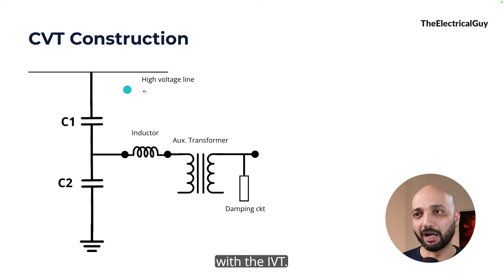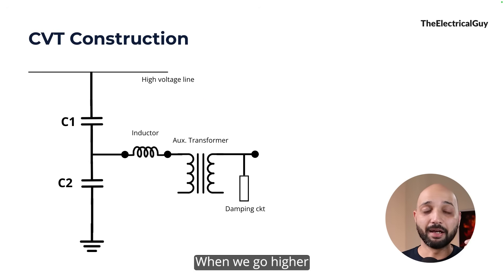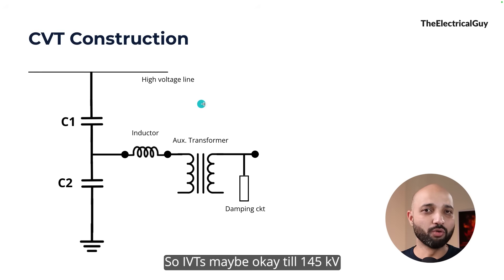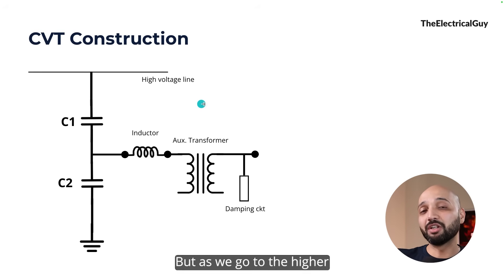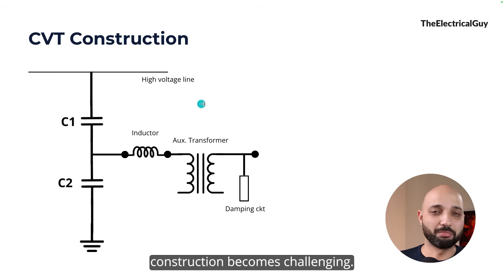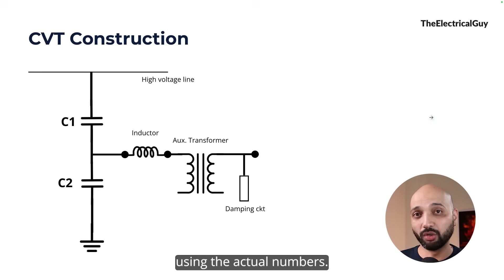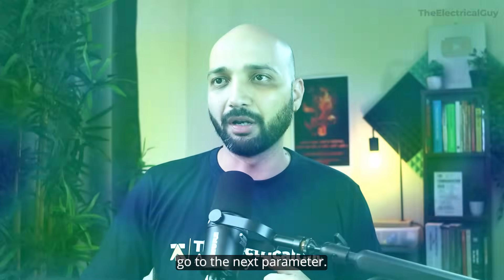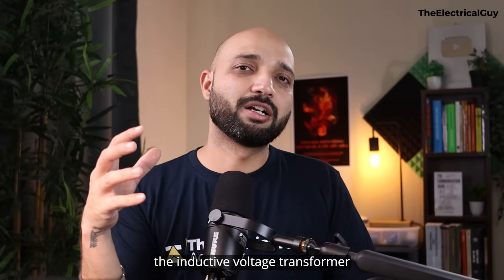This more complex construction of the CVT is actually beneficial as we go higher in voltage levels. The IVT is manageable up to about 145 kV or lower classes, but as we go to higher classes like 420 kV or 800 kV, the IVT construction becomes very challenging. Let me show that with actual numbers as we move to the next parameter: weight.